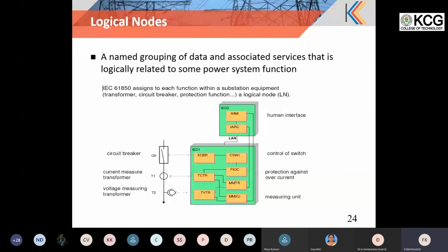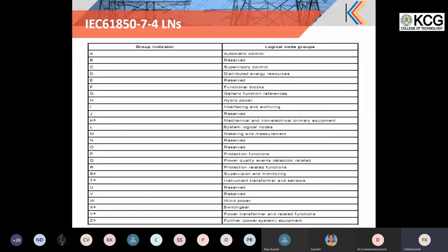So these are the logical nodes, segregated by the first letter. If it starts with A, it is automatic control. If it starts with P, it is a protection function. If it starts with R, it is a related protection function, like disturbance record, everything can be there. If it starts with M, it is a metering and measurement logical node.